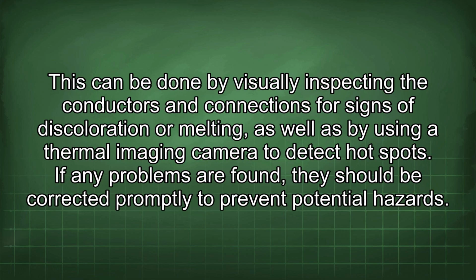This can be done by visually inspecting the conductors and connections for signs of discoloration or melting, as well as by using a thermal imaging camera to detect hot spots. If any problems are found, they should be corrected promptly to prevent potential hazards.